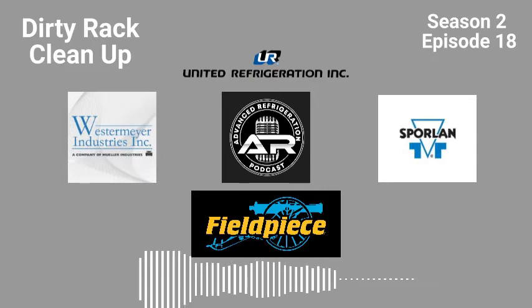I'm not a big fan of doing oil changes. I think it's kind of useless, especially if it's POE oil. I'll just try to clean it up using oil filters. I may change them a couple times, maybe once a day, till I get the debris cleaned up, depending on what it is. If I get a reed breakup and it's in a separator, it could take 3 or 4 oil filter changes, one every day, before you get all that crap out of there. You want the filter to plug up. Do not, I will say this again, do not use the bypass filters.